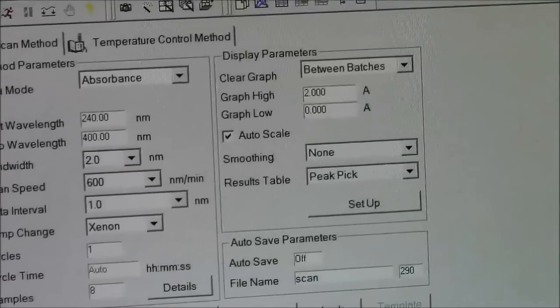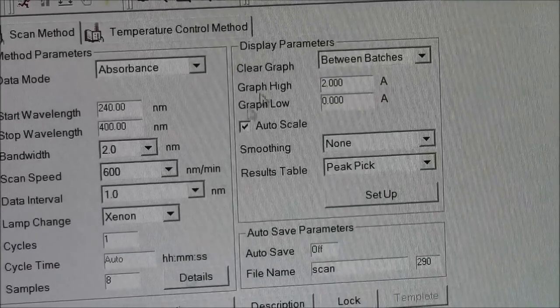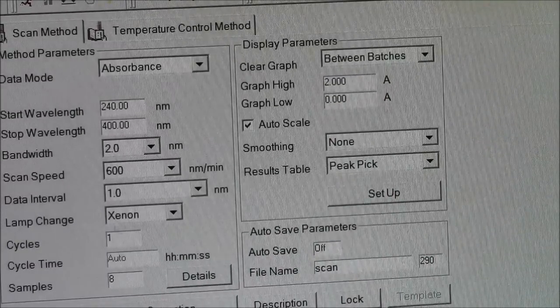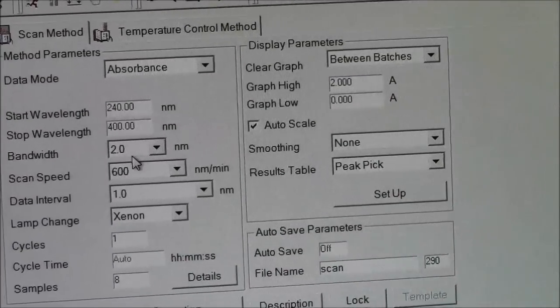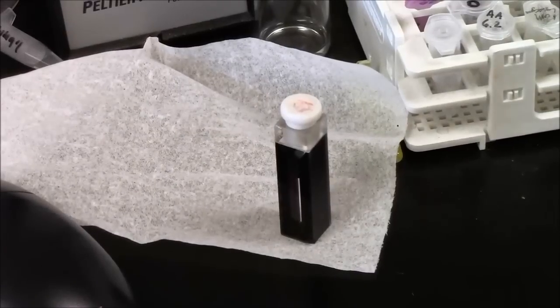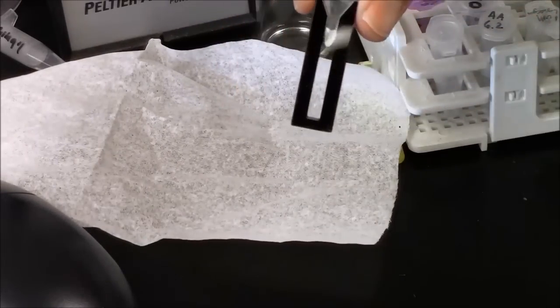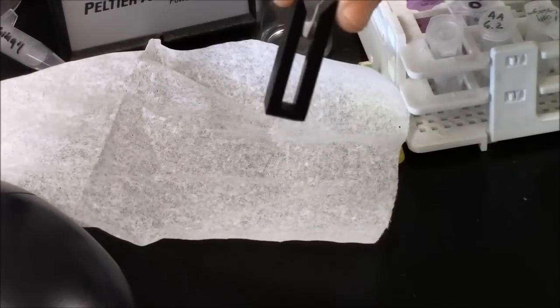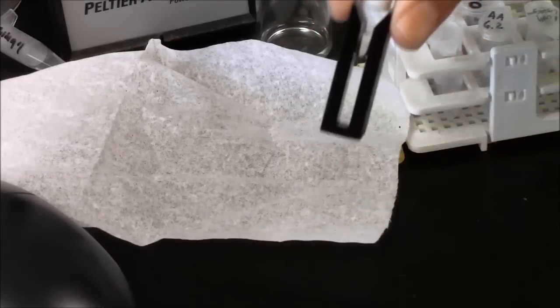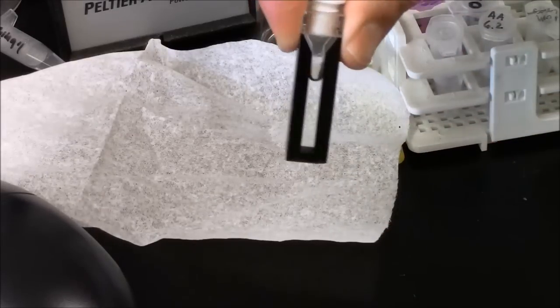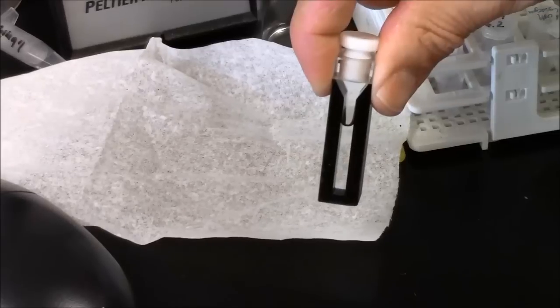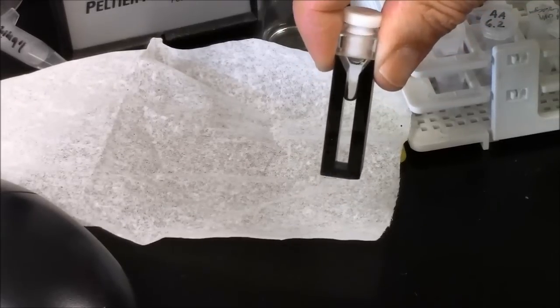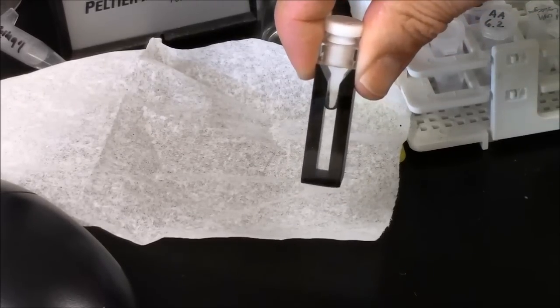On the right side, you shouldn't need to change anything. And we are now ready to scan. To take a spectrum, you need what is called a cuvette. This is a semi-micro cuvette. We use these commonly. Volume is about 1 milliliter. Right now I have pure ethanol in this cuvette. And this will be what I use for a baseline.